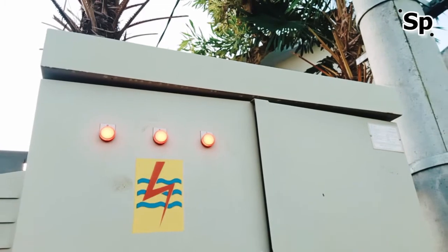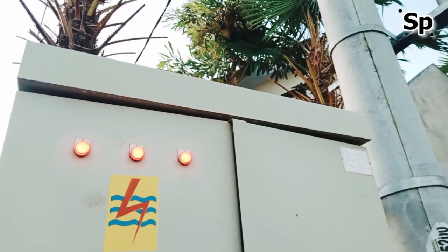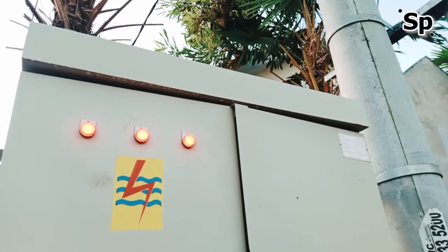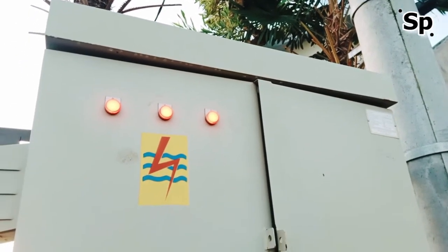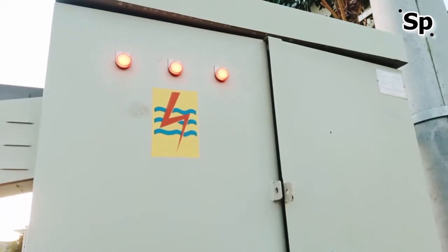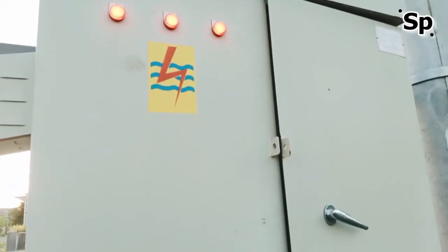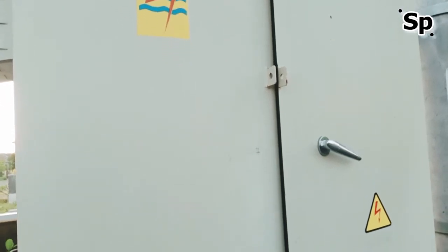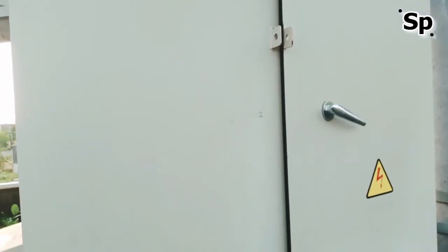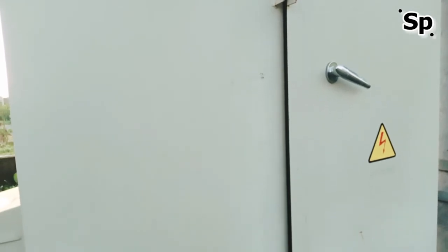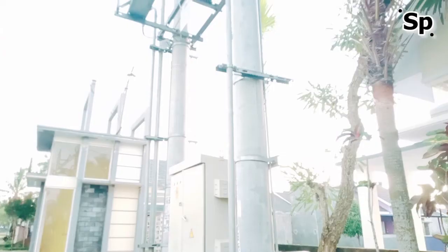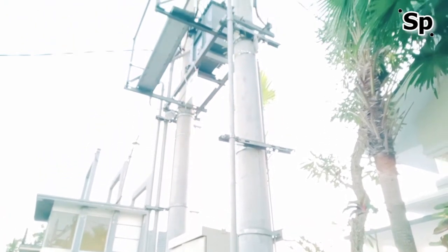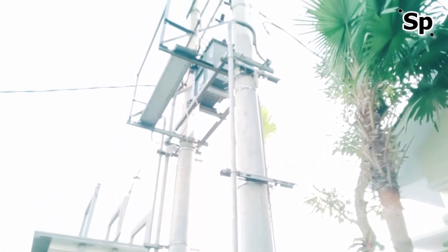Support pole. A support pole is a pole that is installed on a straight power line and is useful for supporting transmission wire and equipment. The force suffered is the weight of the wire and its equipment. This support pole is in the network path and is used with a post pin insulator holder. The height of these support poles varies, ranging from 11 meters to 15 meters in height, with pole strength ranging from 200 to 1200, and can be made of iron or concrete.